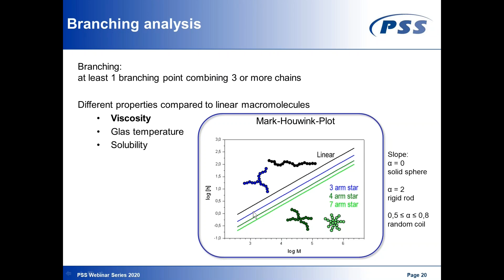In principle, you could also use a multi-angle light scattering detector, but I personally prefer viscosity over the MALS detector in this case, because for viscosity, the extrema go from a slope of 0 for a solid sphere to a slope of 2 for a rigid rod, while the range is much smaller for the radius of gyration. So for a multi-angle light scattering detector, this would vary only in the range of 0.33 to 1. So the viscosity detector is the detector of choice to investigate long chain branching.